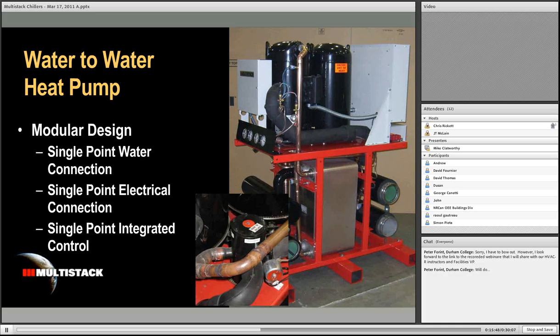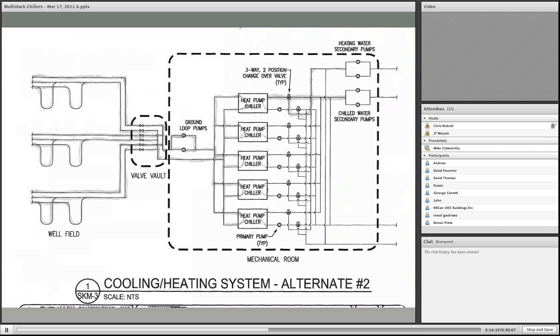So, I'm going to move on, and I want to talk about heat pump technology, because what we've been talking about at this point is really not a heat pump, only in the strictest theoretical sense. We've been moving heat, certainly. Well, a heat pump usually involves a reversing valve and the ability to move heat back and forth bidirectionally at will. So a few years ago, we discovered that modular chillers also make great heat pumps, and so we can assemble some of the largest water-to-water heat pump systems in the world with a single water connection, a single electrical connection, and a single controls connection.